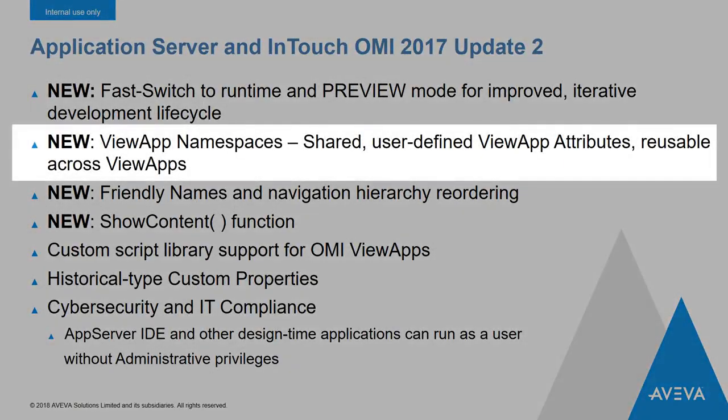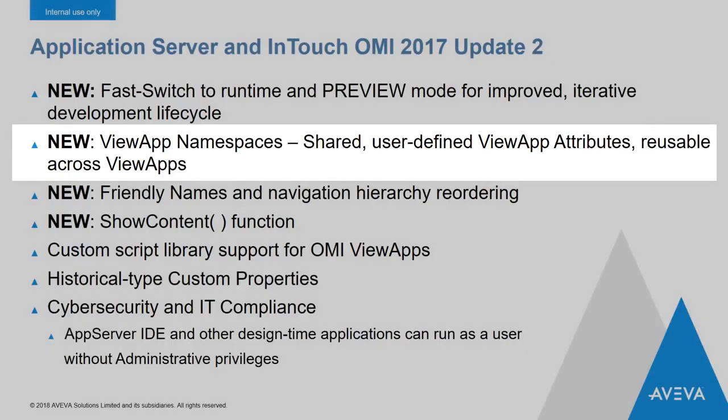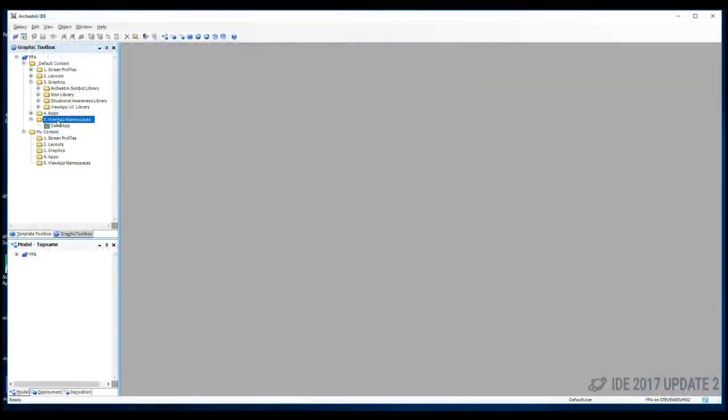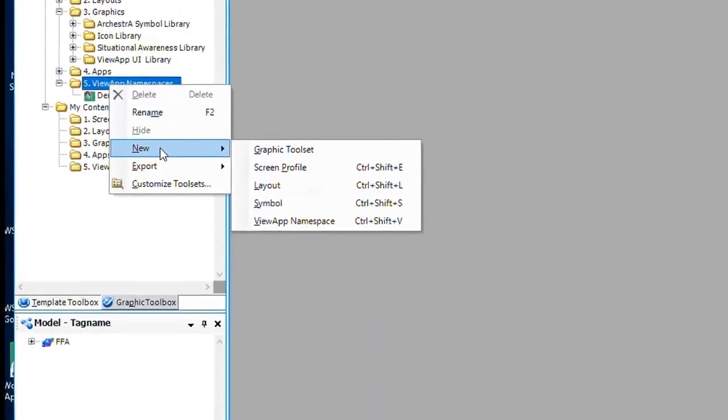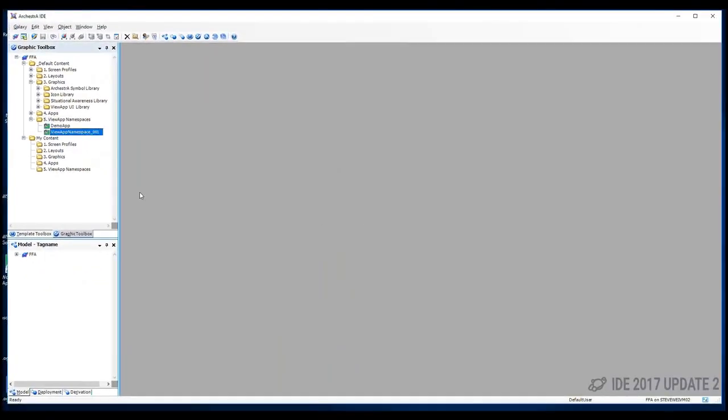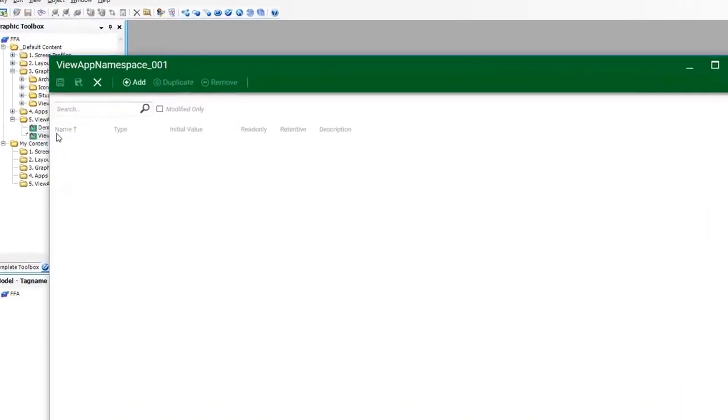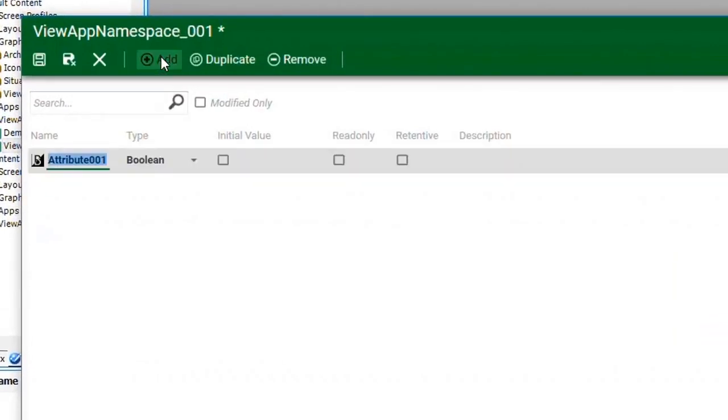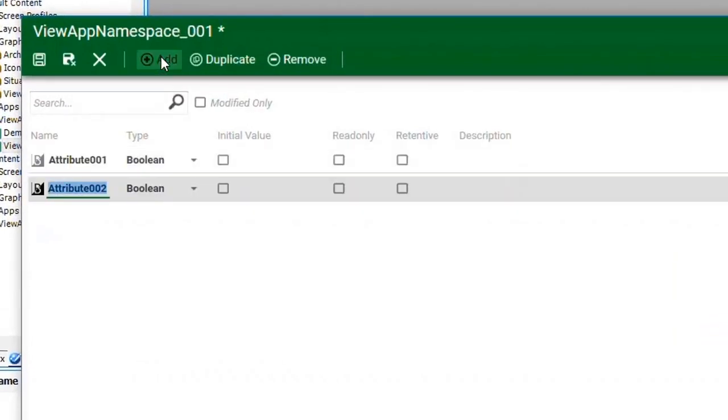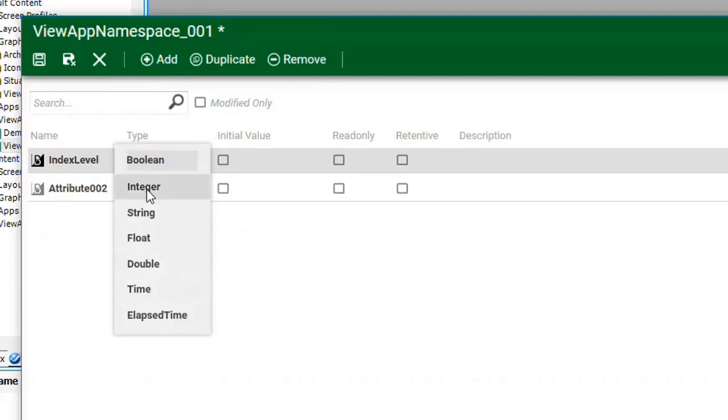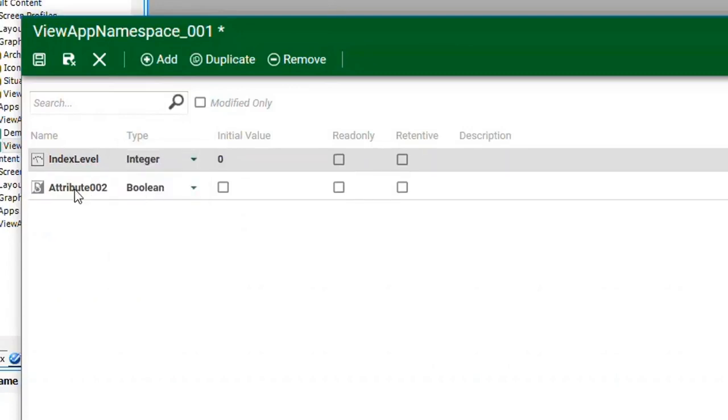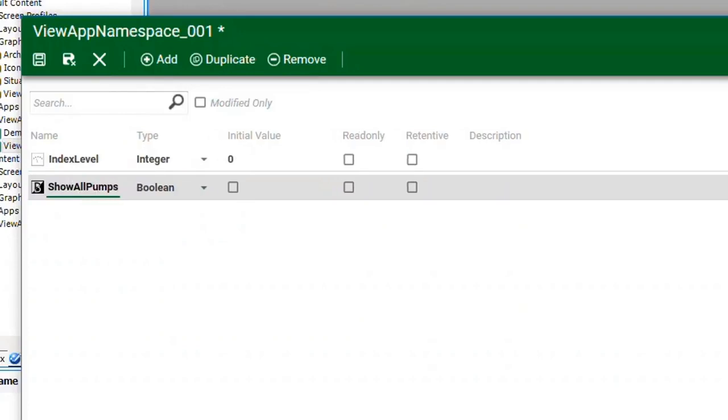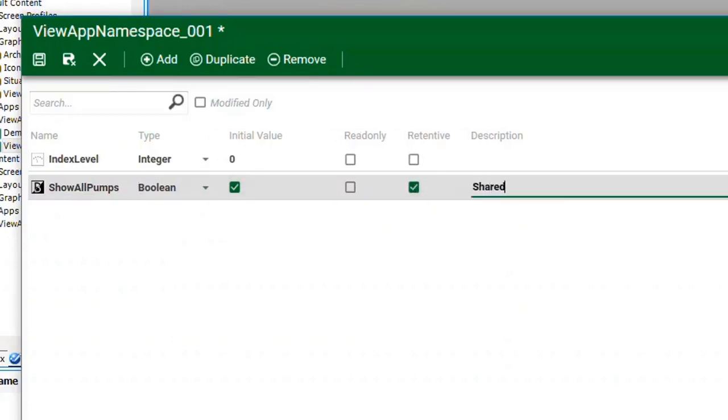Also new to InTouch OMI for Update 2 is view app namespaces. These are logical containers for user-defined attributes that can be used within a view app. You can create a new namespace object in the graphic toolbox. These sit right alongside other shared objects like symbols and layouts. And then in the attribute editor for the namespace, you can define attributes that you want to use within that namespace. The attributes show up in the autocomplete and can be used as a reference in the view app, in layouts, and in the ArchestrA symbol custom properties and scripting. And because they're defined in the Galaxy, they can be used in multiple view apps, just like symbols.